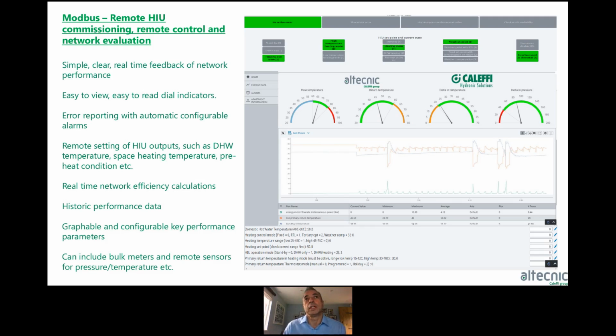You'd access on the menus on the left-hand side all the system data, so the energy data for billing, but you'd also see things like what's happening in the plant room and so on. But what you can see here is a flow temperature, roughly 66, 67 degrees, return temperature on your network as well, then the delta T summarized, and then here differential pressure. You have fault coding at the top, so if there's a fault on the HIU, it'll come up and give you a warning, and that can be linked to alarms that are automatically sent out either via an email or via text message for somebody to actually do something about it. And the parameters for those alarms can be set, so you can tailor them to suit what you want to do on your project.